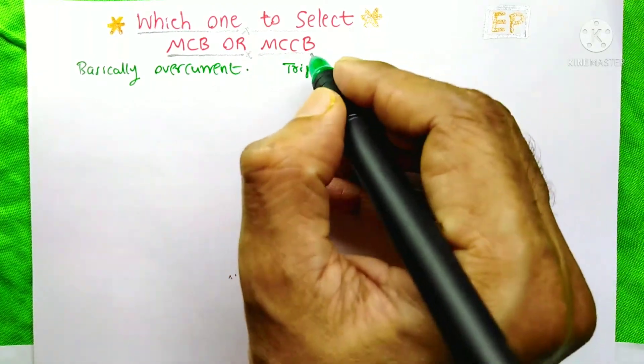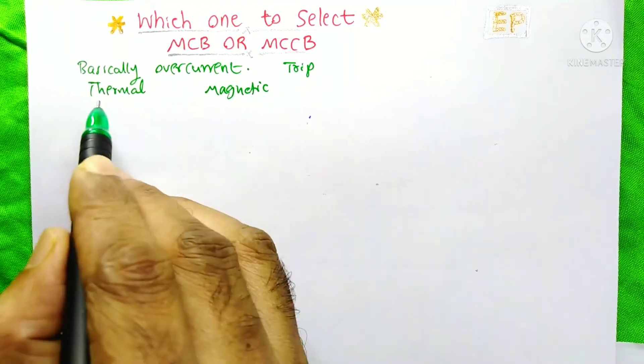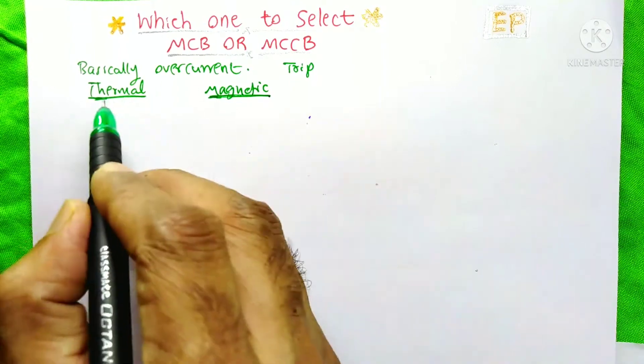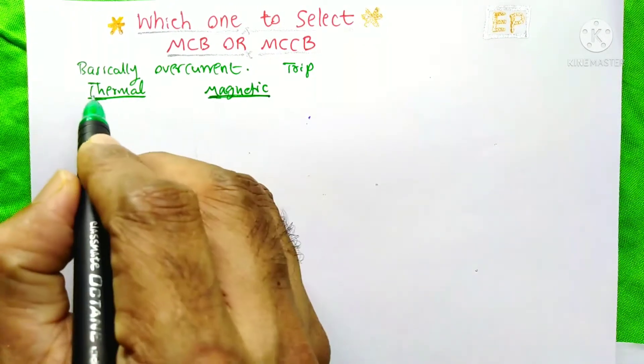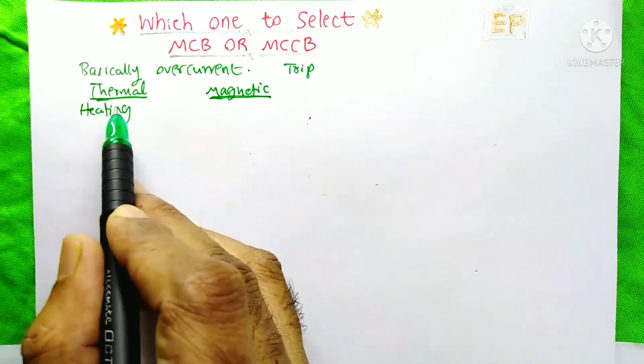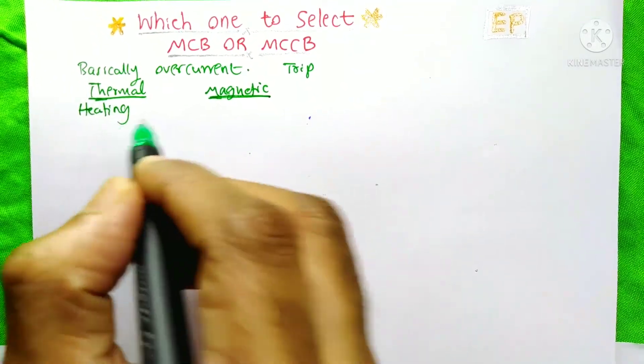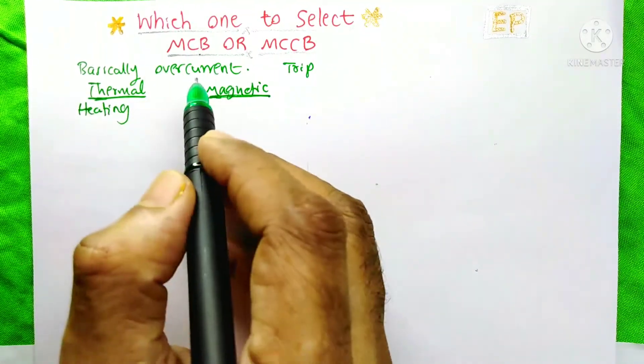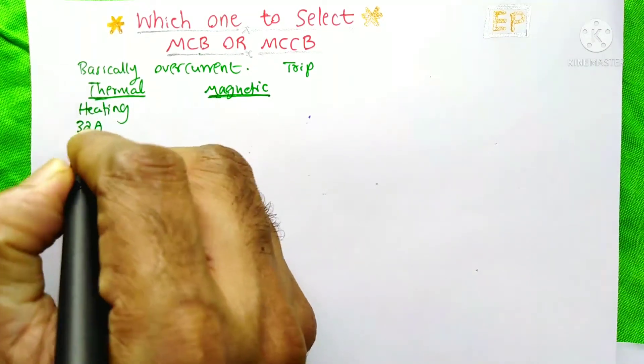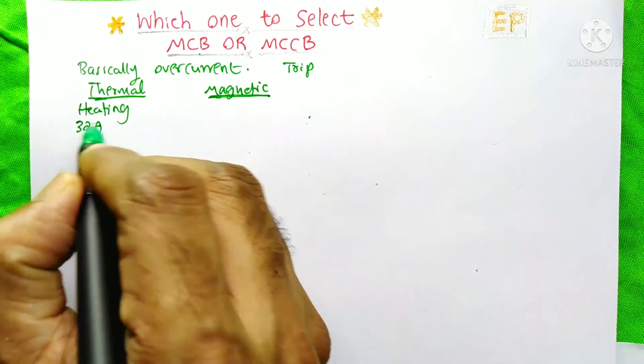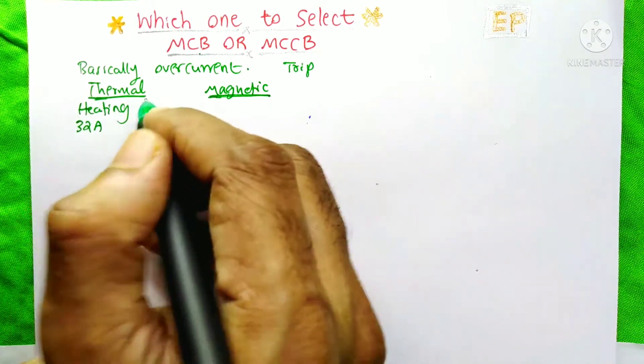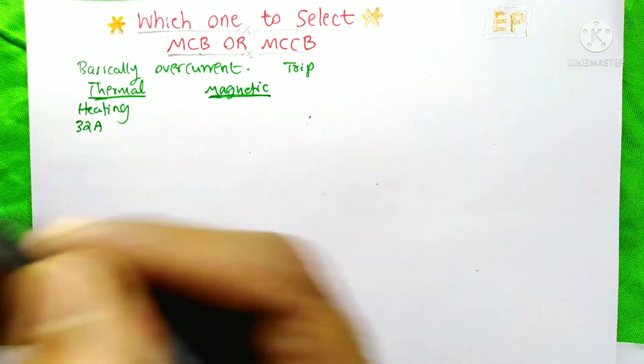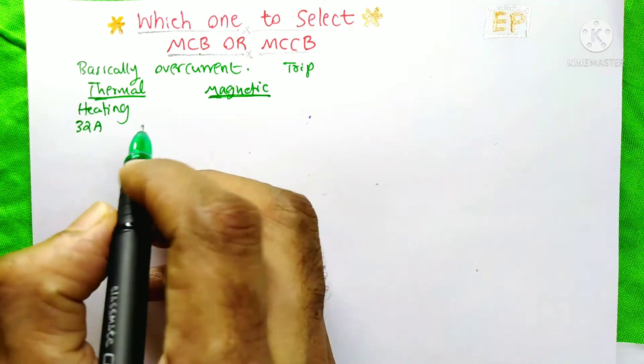Both MCB and MCCB work on the same principle. Both devices have two tripping mechanisms: the first one is thermal tripping and the second one is magnetic tripping. Thermal tripping, as the name indicates, is related to heating. Whenever the current increases beyond the rated current — for example, if the MCB or MCCB is rated for 32 amperes and the current is 33 or 34 amperes — the bimetallic strip inside these devices will heat up due to this overcurrent.